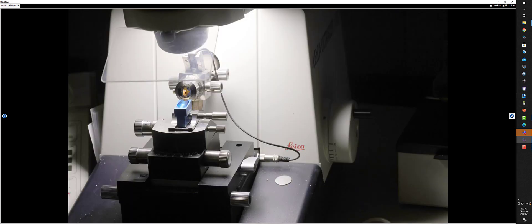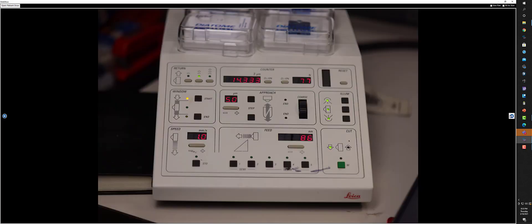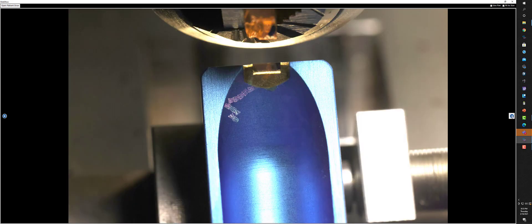Then you take that to the ultramicrotome for your 70 nanometer slices. That's controlled by this controller that can give you estimates on how fast the knife advances and all the parameters that determine how to get really good slices. This is what you see when you're operating the microtome. Here you can see the pyramid that I have to slice. You bring the knife up to it and start slicing. Here you can see the different interference colors. These are all way too thick for an electron microscope.